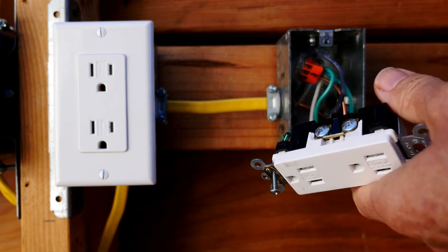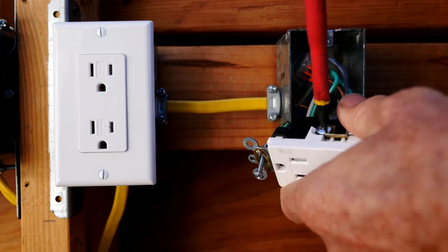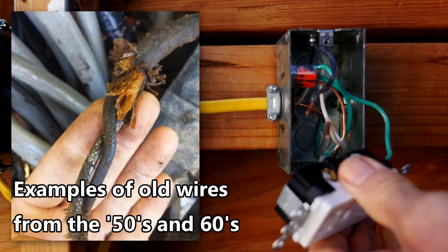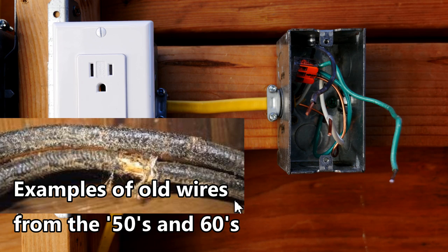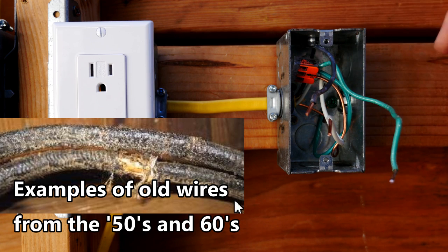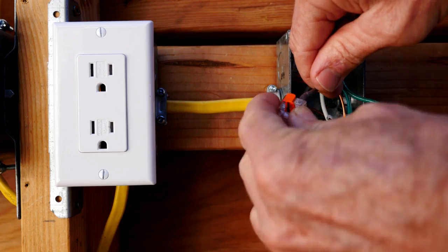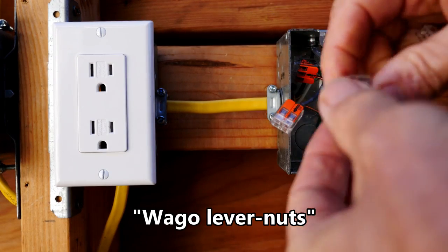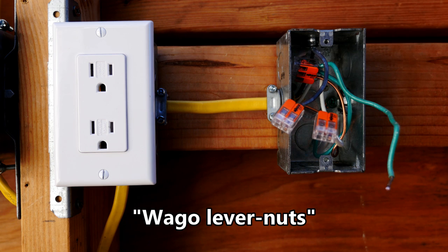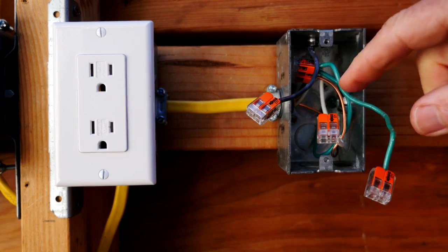One of the big reasons for reverse polarity receptacles is that in older houses, the hot wire and the neutral wire both turn gray and they're really the same color — houses from the 50s and 60s. It's really difficult to tell just by looking at them, and sometimes people guess wrong and you get a reverse polarity receptacle. So I'm going to show you how to identify which is the hot and which is the neutral. I'm going to put Wago lever-nuts on the ends of the wires for safety, and I'm going to temporarily turn on the electricity to make a test to determine which is the hot and which is the neutral.